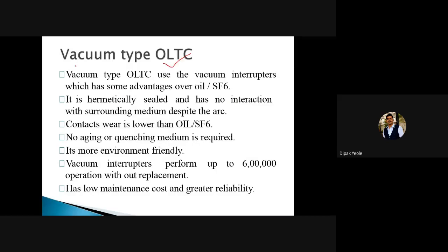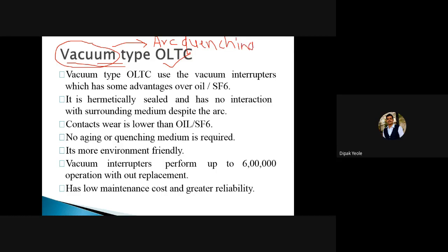There is one type of on-load tap changer — vacuum type — in which the vacuum material is used as the arc quenching medium. The spark which we observe can be quenched with the help of this vacuum. To create a vacuum, it involves a tedious process. We have to remove the air from the particular chamber and make sure that no new air takes place inside. This vacuum type OLTC uses vacuum interrupters which have some advantages over oil or SF6.